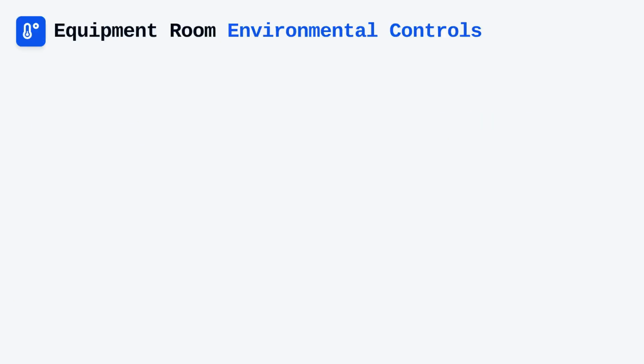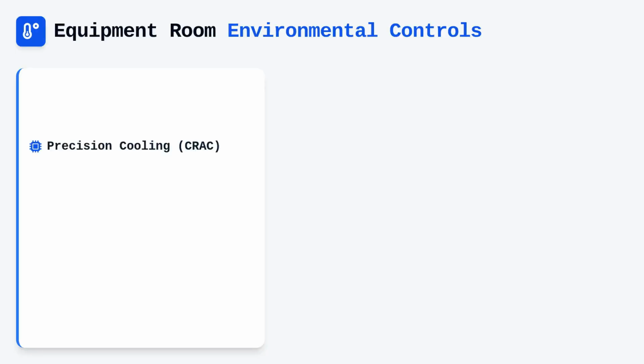Environmental controls within the equipment room must be managed with cold, hard logic rather than guesswork. High-density server deployments generate significant heat loads that demand professional-grade precision cooling solutions, such as computer room air conditioning units. These systems are not merely standard air conditioning. They are dedicated, 24/7 units capable of maintaining stringent temperature and humidity set points.